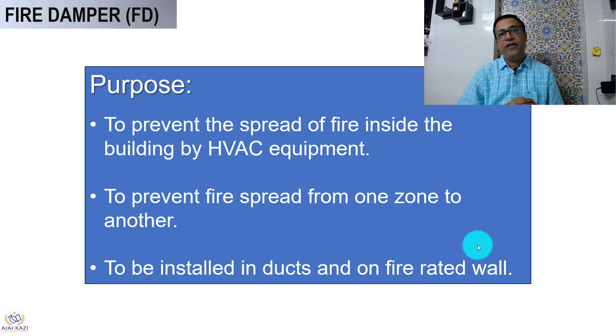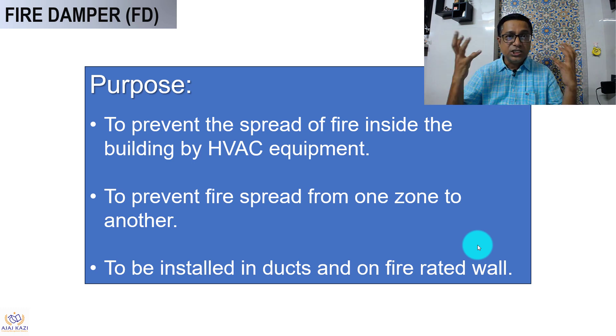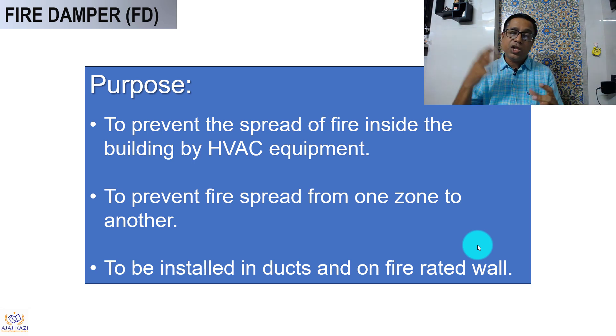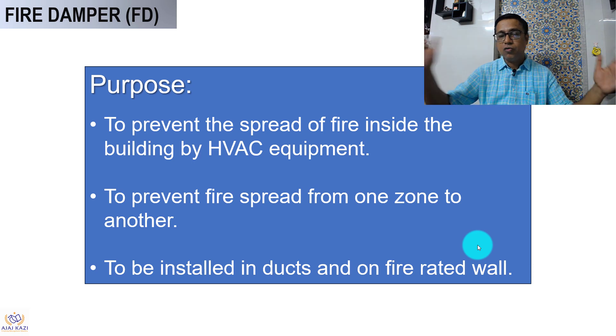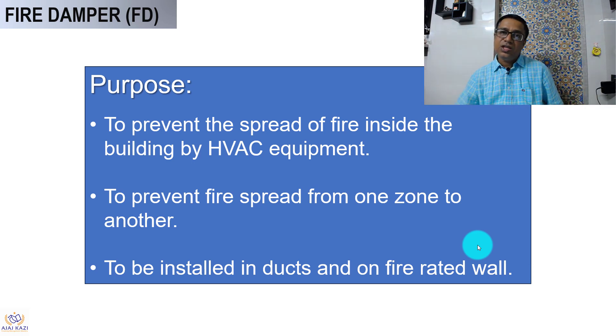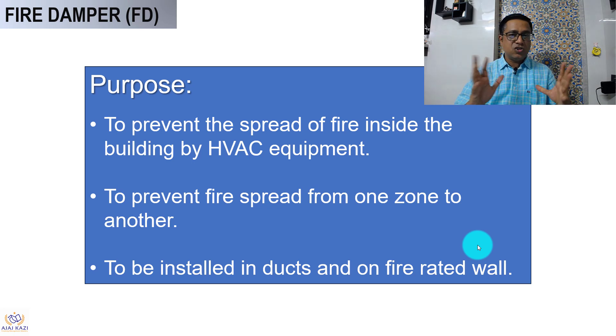The next damper is the fire damper, also called FD. This is to prevent the spread of fire inside the building by the HVAC equipment. It is installed after the HVAC equipment and also used to prevent fire from spreading from one zone to another. If you have two zones with a fire-rated wall, the fire damper prevents fire from crossing between them. These are installed in ducts as well as on the fire-rated wall.